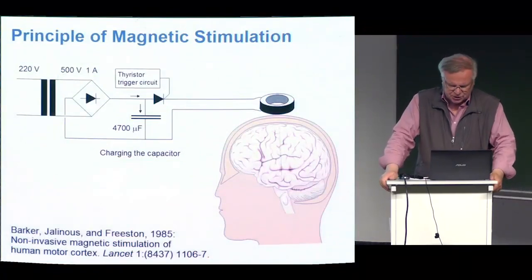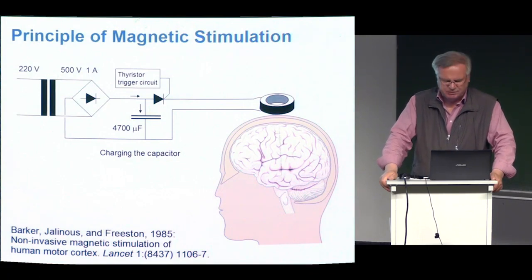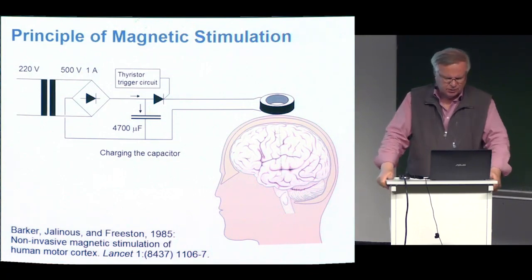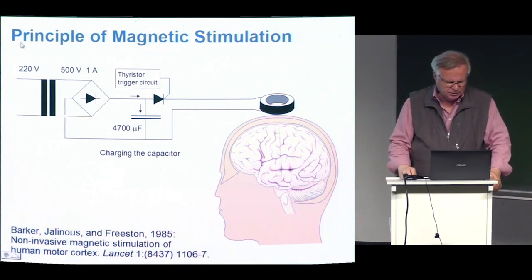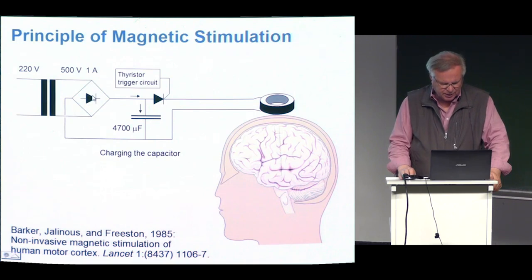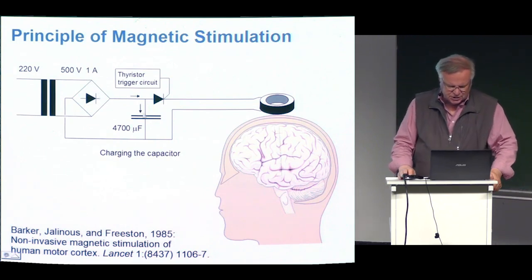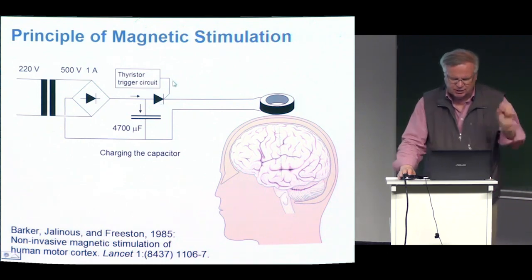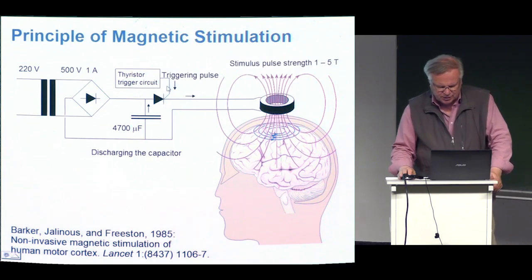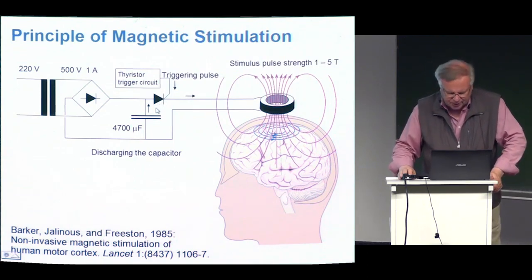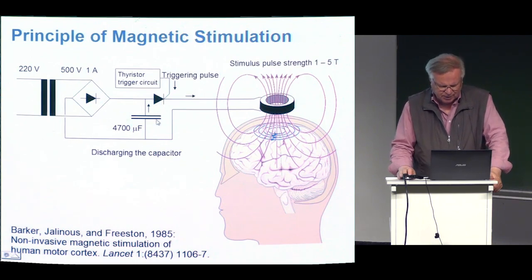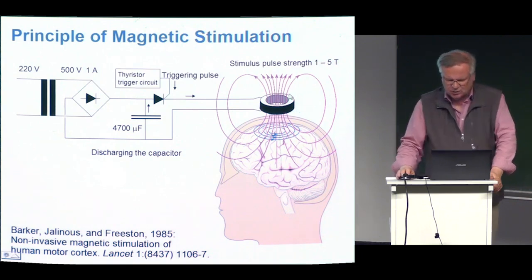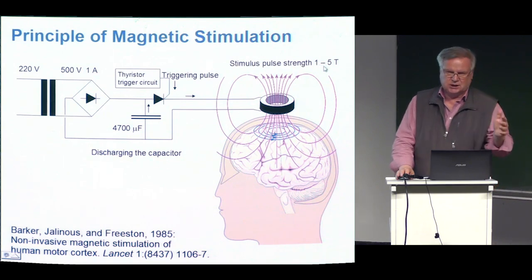Today, magnetic stimulation is made in this way. This is a much simplified circuit, but in principle this is how it works. There is a current source, transformer and rectifier, which charges a very large capacitor. Then there's a thyristor switch. The thyristor is triggered, and with a triggering pulse it opens, permitting current from the capacitor to flow through the coil, inducing a magnetic field with a strength of 1 to 5 teslas — a really strong magnetic field.